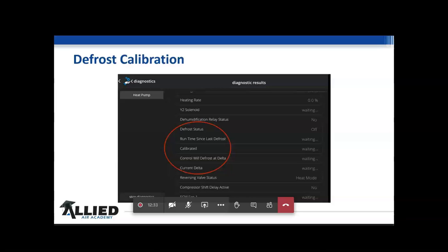It's going to do a self-internal, and I hate to call it calibration, but that's what it is, a self-internal calibration. Because again, I go back to what I said, if we ran this thing or started it up on a cold day, well, then it's going to be much different than a mild day. That is that first initial sacrificial defrost that they do. That is just to get a nice baseline started. Once it gets the baseline started, it'll always sit there and do this. But you can go to the stat, look at this, especially while you're on the call, and see exactly when, and it'll tell you in real time that delta. It'll start reading it and it'll start narrowing down, and by the time it gets right there, boom, you got it. Now the Wi-Fi version, or the white stat, does the same thing as well.